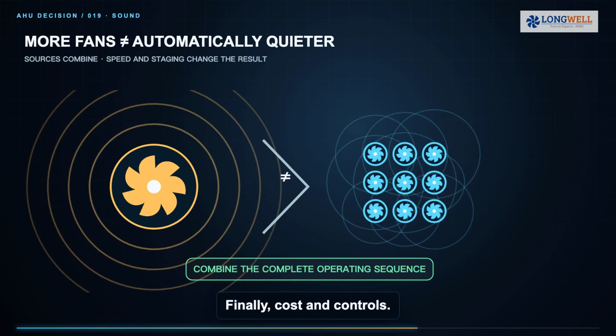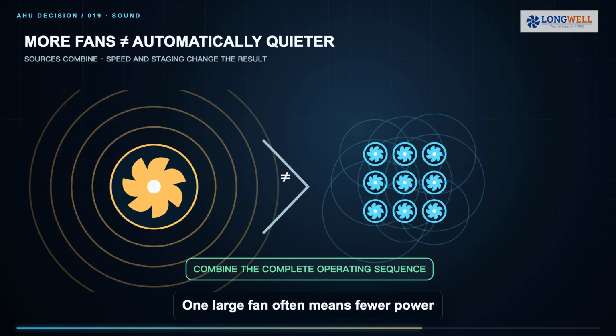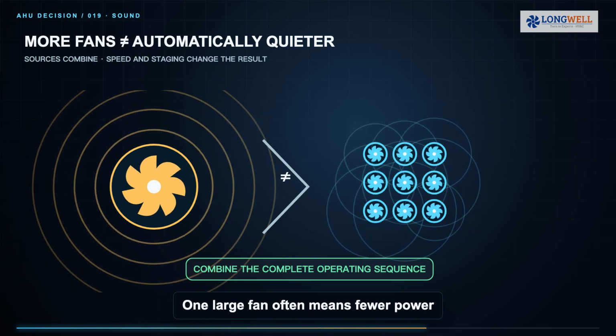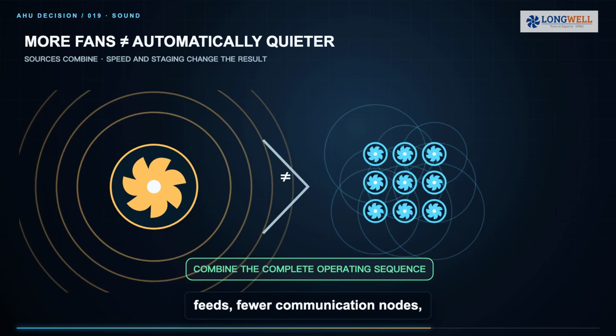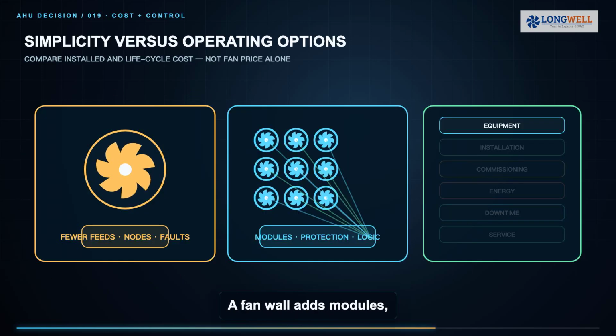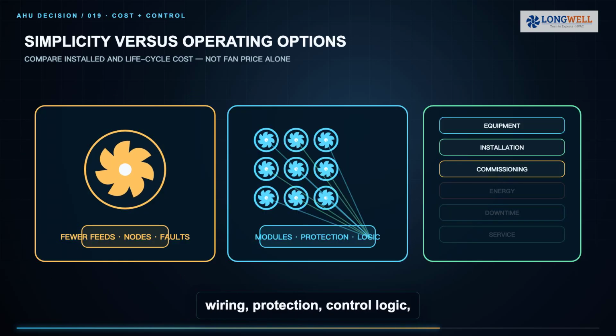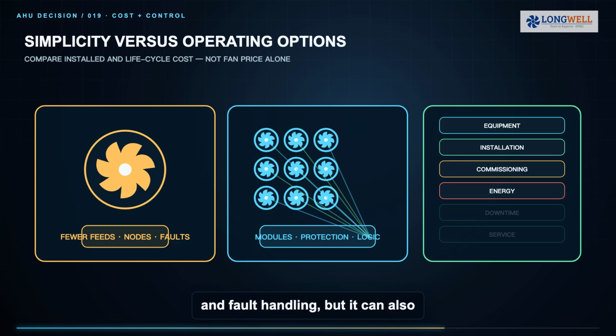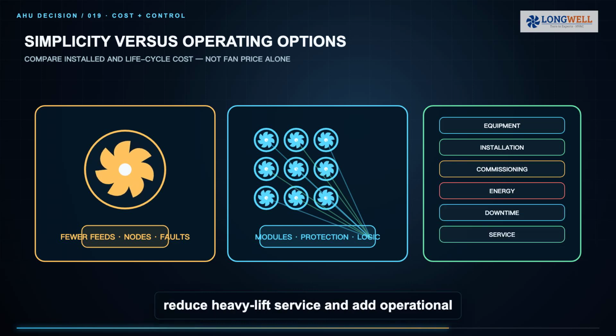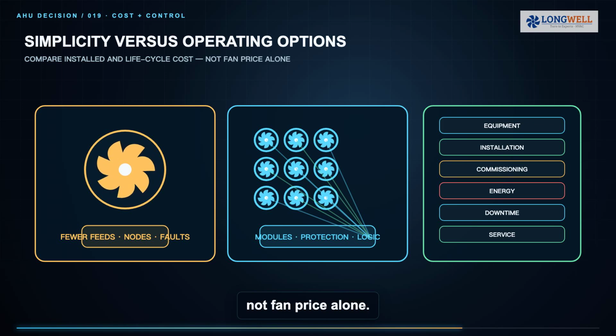Finally, cost and controls. One large fan often means fewer power feeds, fewer communication nodes, and simpler commissioning. A fan wall adds modules, wiring, protection, control logic, and fault handling, but it can also reduce heavy lift service and add operational flexibility. Compare installed and lifecycle cost, not fan price alone.